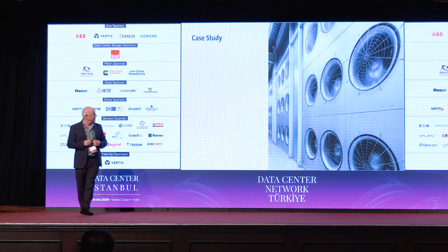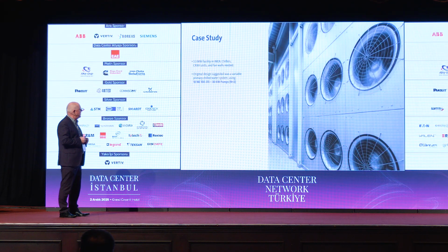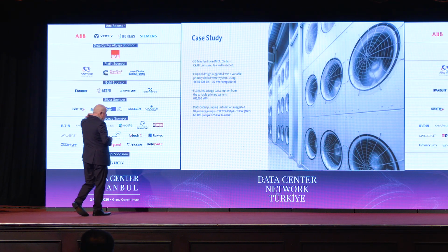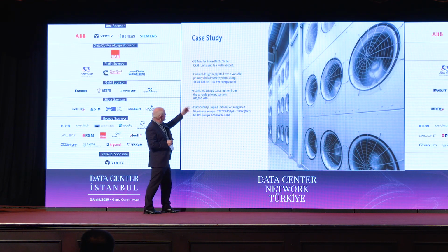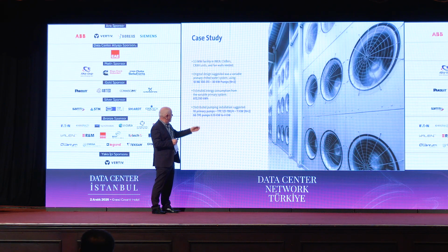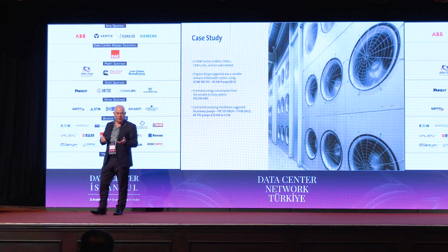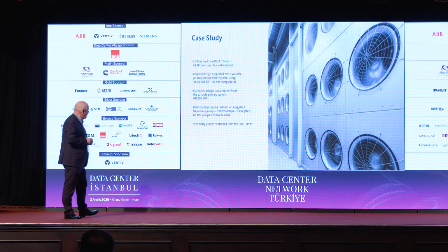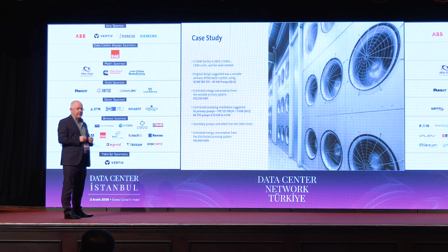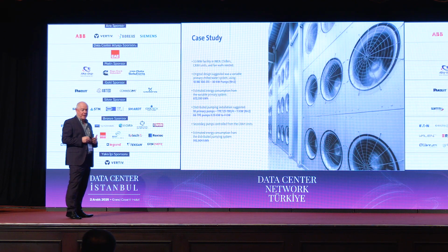And if we look at a case study, and this is in this region, where we've had 10 large primary pumps, N+2, and we've replaced them with 10 primary pumps which are smaller. So we've gone from 30 kilowatt down to 11 kilowatt, and then quite a lot of secondary pumps, which are quite small pumps as well. The energy savings in this case turned out to be almost 400,000 kilowatt hours. And as we go up bigger in systems, and as we go to systems which have more diversity on them, you're going to see more and more energy savings as well.